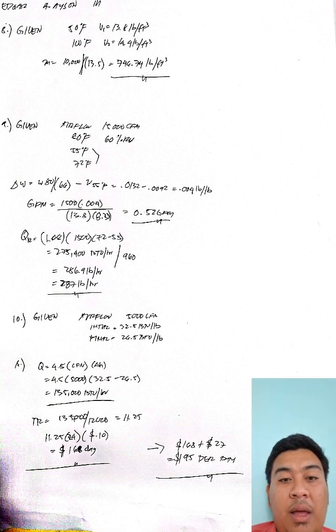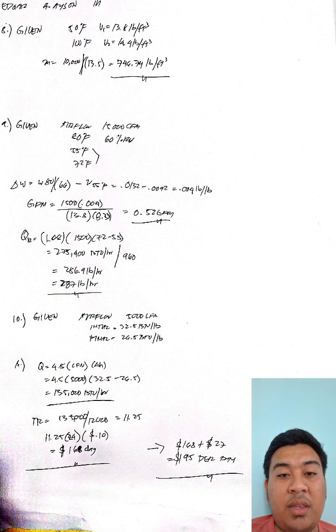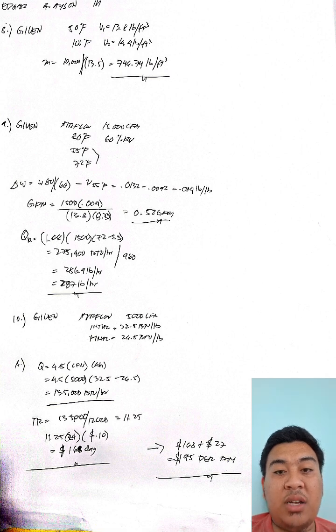For B, to lower the relative humidity at a constant level, we have a cooling load of 11.25 TR times 24 hours a day, which is equal to 270 ton hours. Then the cost is about 270 times $0.10, which is equal to $27 per day. Then the reheat load is roughly equal to the cooling load for the sensible reheat. So steam is 135,000 BTU per hour times 24 over 960, which is equal to 3,375 pounds per day.